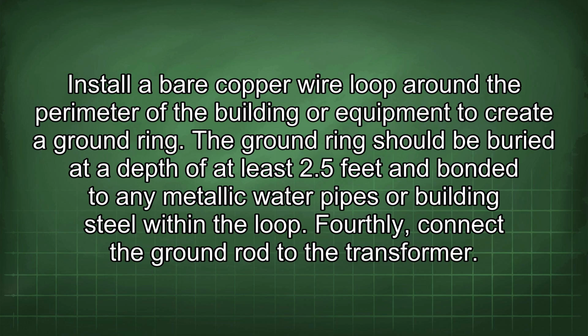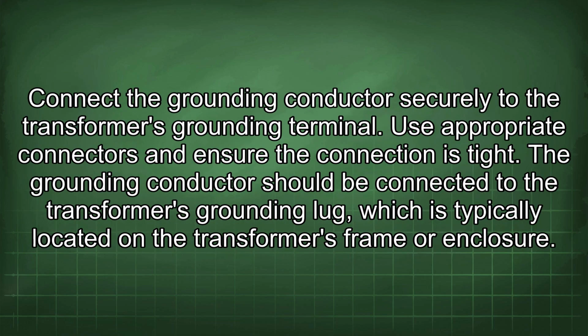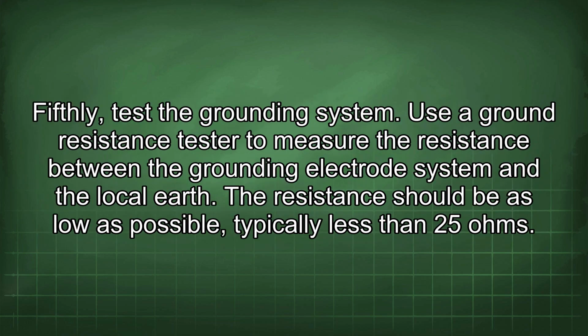Fourthly, connect the ground rod to the transformer. Connect the grounding conductor securely to the transformer's grounding terminal. Use appropriate connectors and ensure the connection is tight. The grounding conductor should be connected to the transformer's grounding lug, which is typically located in the transformer's frame or enclosure. Fifthly, test the grounding system.